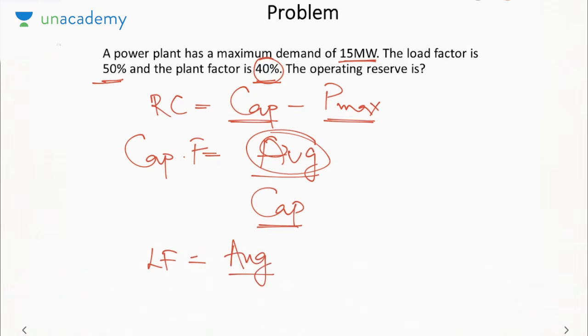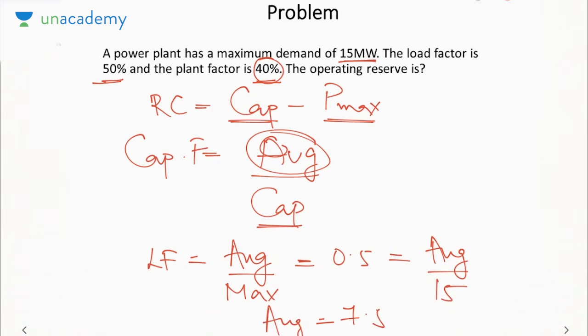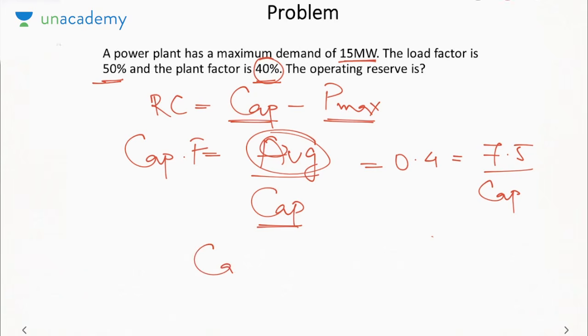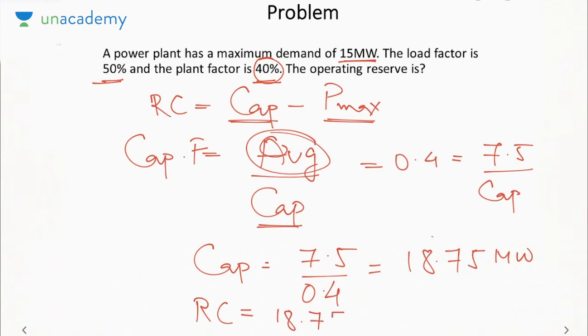If we need to find capacity, average can be calculated from load factor. Load factor is equal to average by max. This is equal to 0.5. It's equal to average by maximum, which is 15. So that means average will be 7.5. Now this capacity factor 0.4 is equal to 7.5 by capacity. So capacity will be 7.5 by 0.4, that is 18.75 megawatt. Then reserve capacity will be 18.75 minus 15, which is 3.75 megawatt. Okay, so that is the reserve capacity of the plant. Is it fine? So first you must look at the term that is being asked and the data that is given. So you must create a map using the expressions that we have studied to determine the required value.